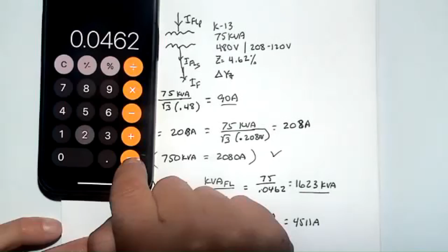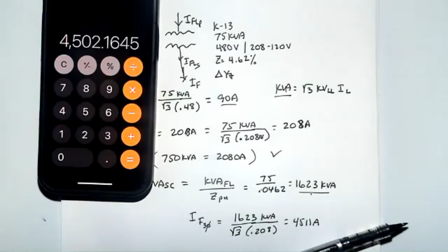But anyway, our full load amps and our fault kVA are important. And so you can see that we're using the same equation, which is kVA equals square root of 3 kV line to line times I line. And if that kVA is our fault kVA, which is what we used here, we can then calculate the fault current here. So the equations are all the same. It's either kVA full load or rated, or kVA fault. And the way you get kVA fault is divided by the impedance. But again, if you can remember that 208 volt and 208 amps, that's going to come in really handy.